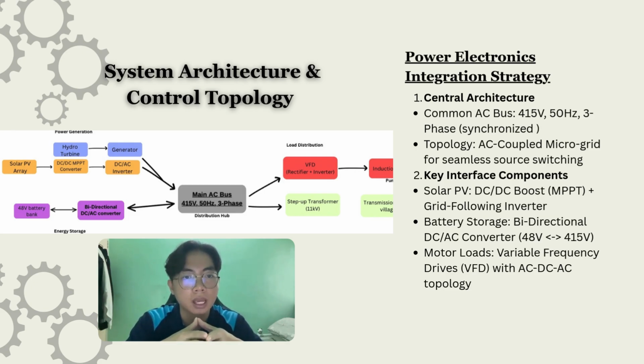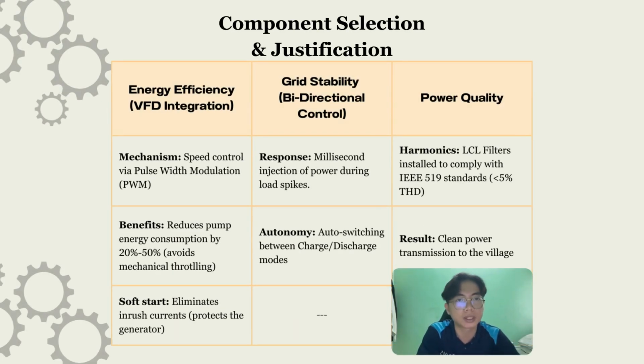Finally, for the heavy machines, we didn't just wire them directly, but we use VFDs, or variable frequency drives, to isolate them, which I will explain on the next slide. The reason we design our system this way comes down to three things: efficiency, stability, and safety. For the first part, efficiency: using VFDs on the pumps lets us control the speed electronically. Instead of using mechanical valves to choke the flow, which can waste a ton of energy, we just slow down the motor. That saves us around 20 to 50% on power.